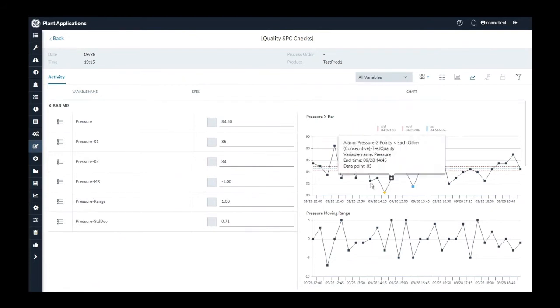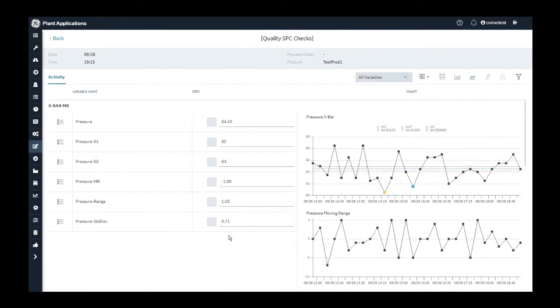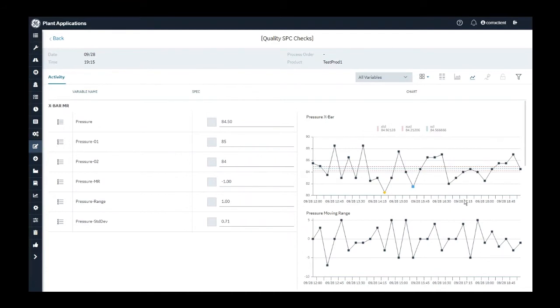Plant Applications SPC chart looks at the last N number of data points, where N is a configurable parameter. For this demo, I have set this as 30 data points. So it looks at the last 30 data points, observes a pattern within the data, and determines the state of the process. Now looking at the state of the process, you can clearly know whether your process is controlled within your calculated control limits or not.